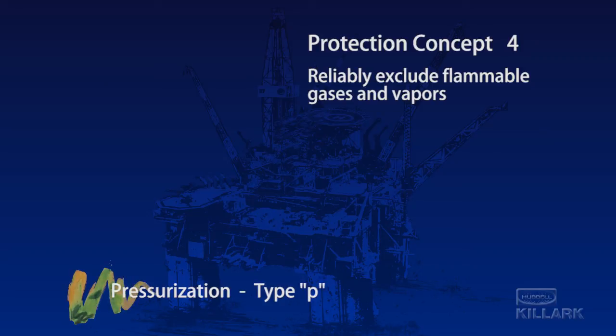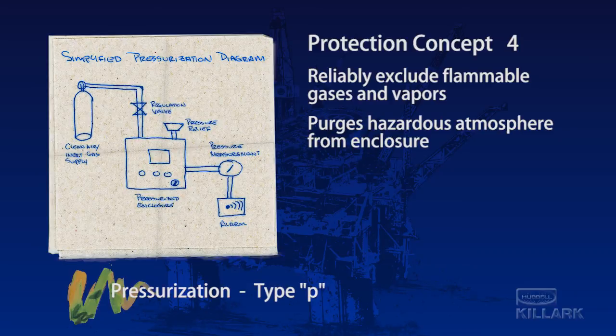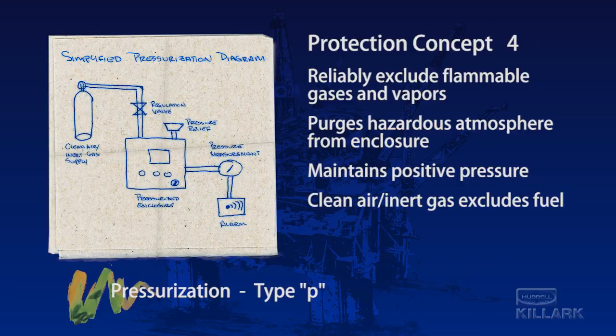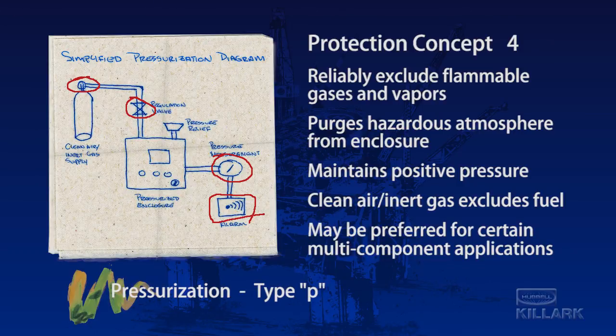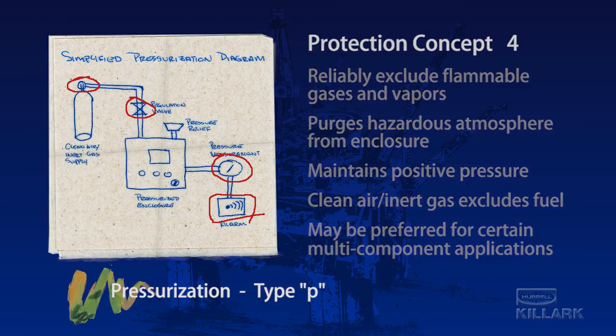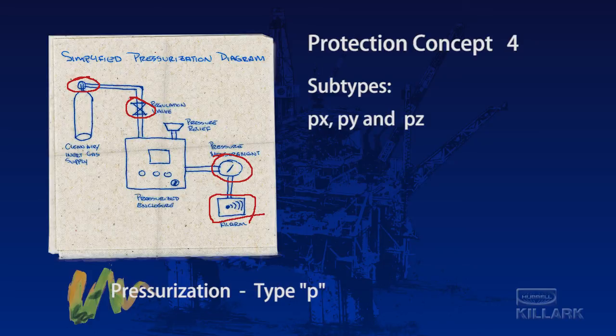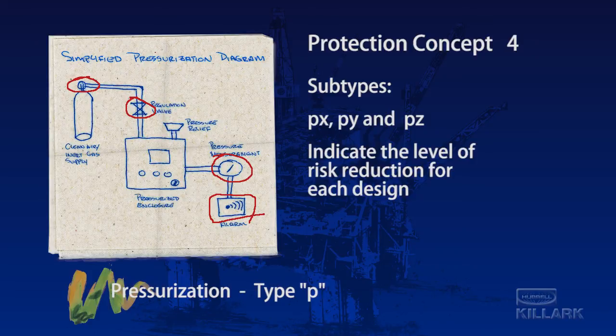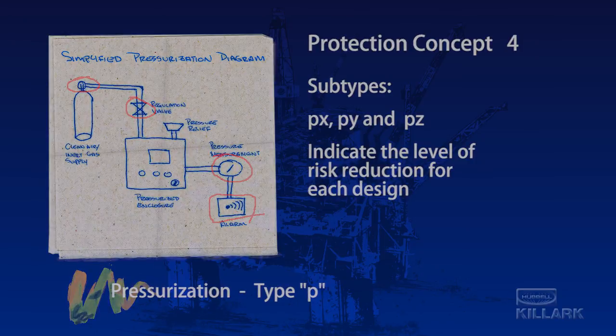Pressurization is an engineering technique that purges the combustible atmosphere from the apparatus enclosure and maintains positive pressure within the enclosure throughout the time that it is energized. Using blowers with a source of clean air, compressed air, or bottled inert gas, the positive pressure prevents the entrance of the ignitable material. The operating, pressure sensing, measurement, and alarm features that must work together to provide Type P pressurization can be quite complex. However, this can be the preferred method for creating overall protection in multi-component power and control panels, as well as entire control rooms. The subtypes PX, PY, and PZ indicate the level of reduction in the explosion risk achieved by each of the pressurization designs.